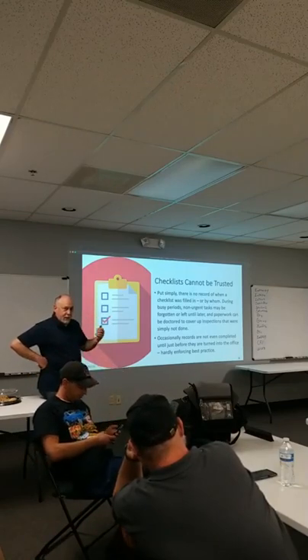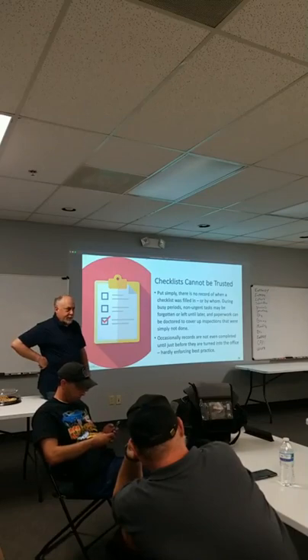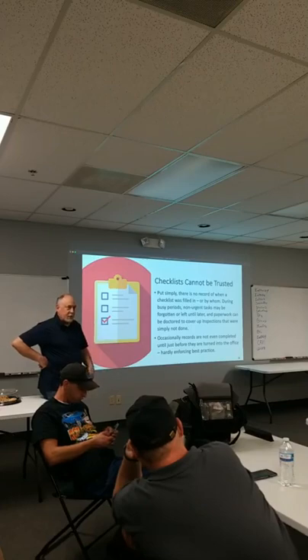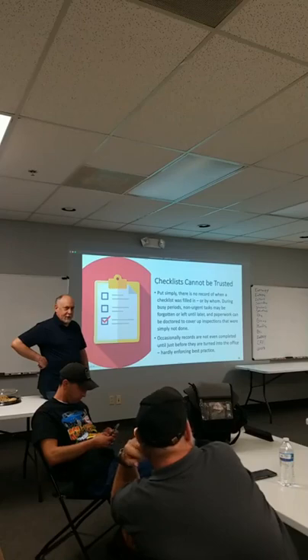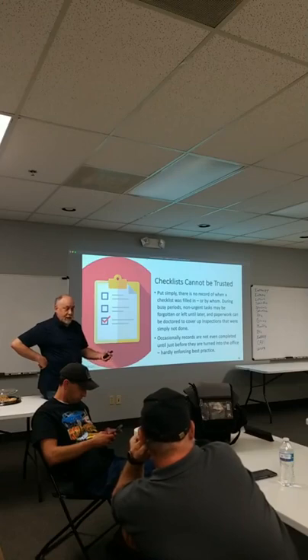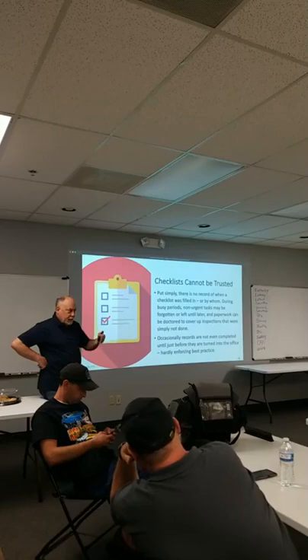I said, come here and sit down for a minute. So I pulled out a psychrometric, temperature-pressure chart, and I said, what was your pressure reading? And what was your temperature reading? That superheat just doesn't add up. Let's look at the subcooling. It seems like you don't remember too much of this stuff. And he was just pencil whipping his paperwork. You start going back and looking at all the invoices and all the incrimination the guys were doing. They were literally copying down other guys' invoices or check sheets.